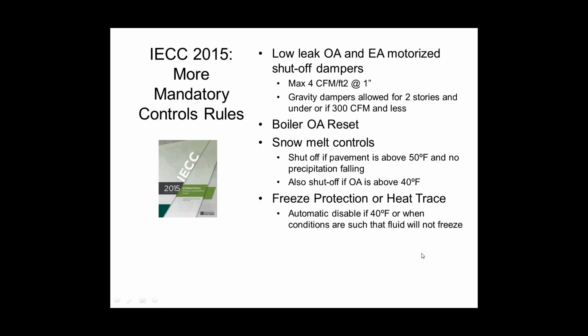Oh, okay. If you're going to have freeze protection on pipes, like heat trace tape on your pipes, you have to have an automatic control that disables them whenever it's 40 degrees. So the controls have to be wired up for that. It says, or when conditions are such that the fluid will not freeze. That language is there to accommodate things that are not plain water. So if you have something with glycol, you might have a different setting. If you have a different unrelated fluid for some reason, you might have a different setting. But if it's just plain Jane non-glycol water, 40 degrees is your code required setting.